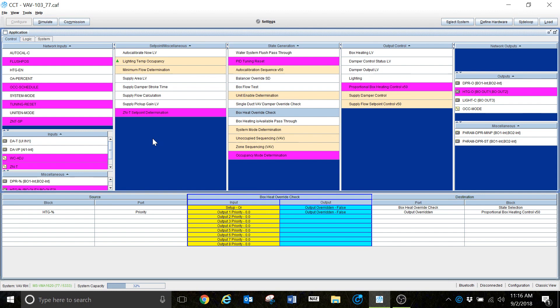This is just the basic way of navigating the software. The more you use it, the more familiar with it you will become. It takes a while to really understand how the logic flows inside of this. You accept the fact that you're going to make mistakes. One thing I would strongly suggest is to regularly save your work. If you have a program uploaded from a controller that you're needing to modify, save that as a different file name so that if something happens, you can at least get your controller back to running the way it was previously.